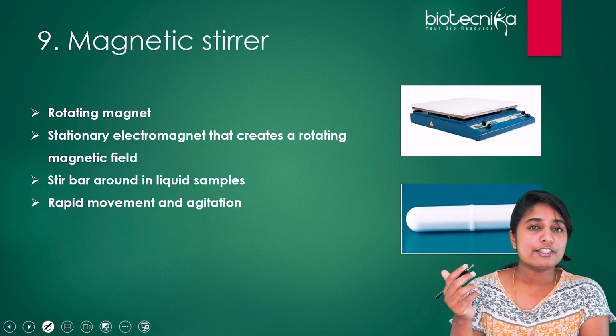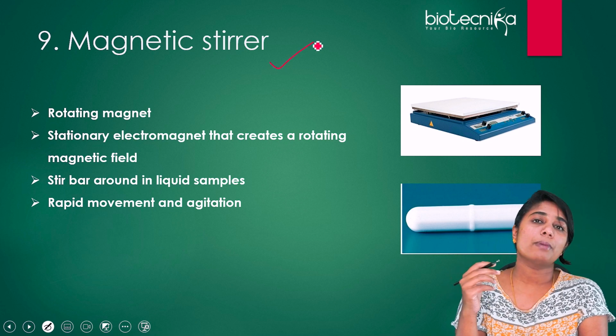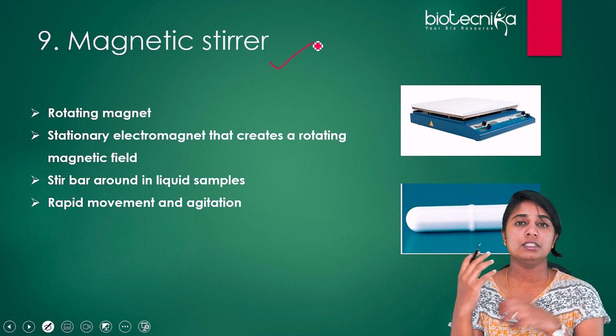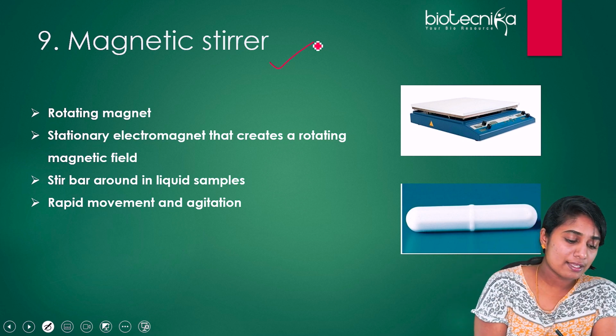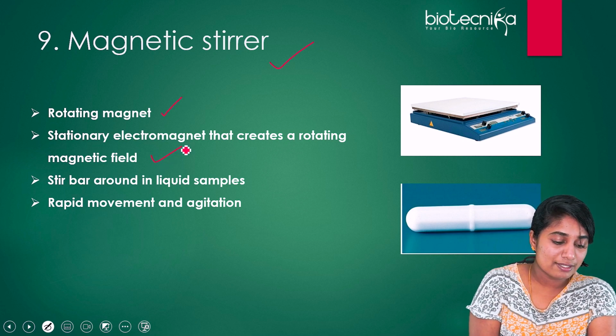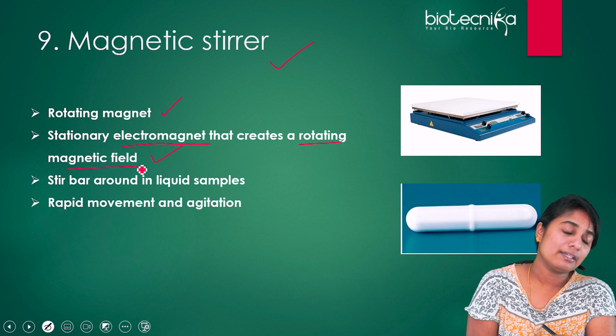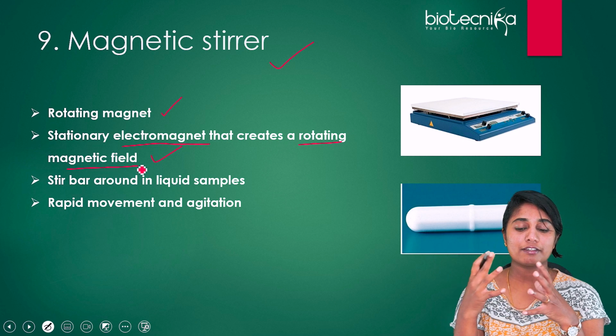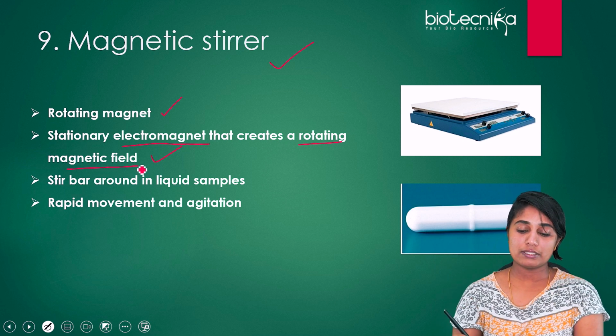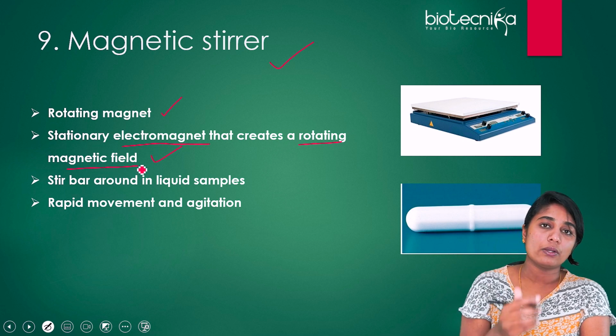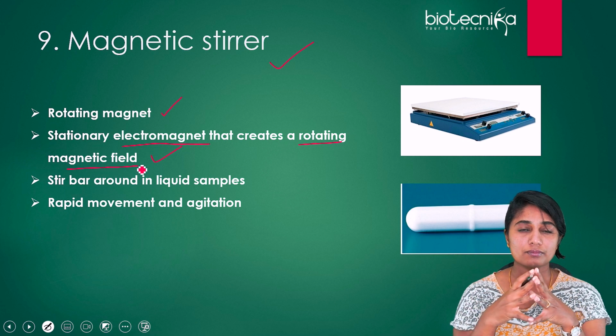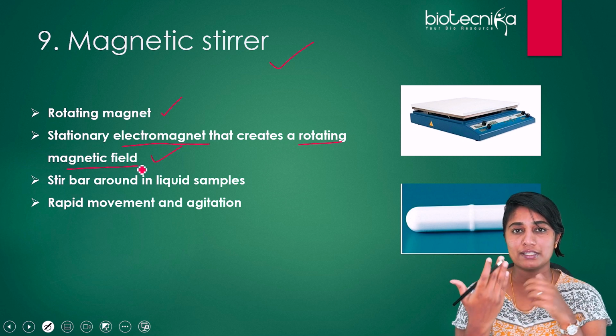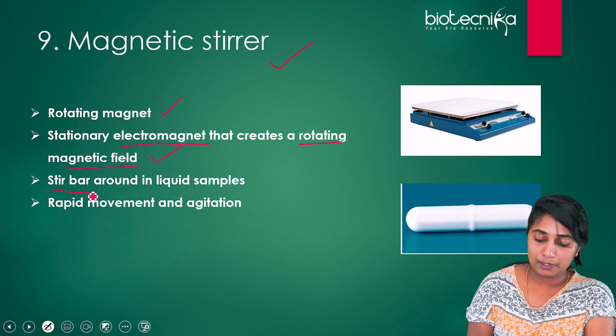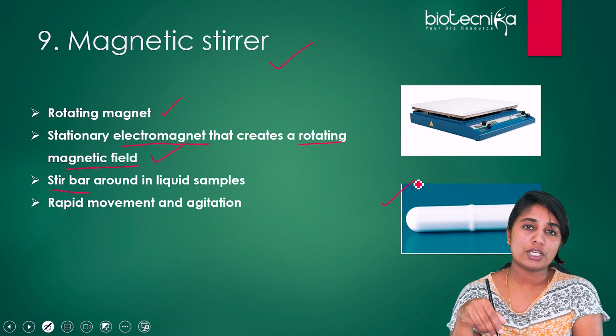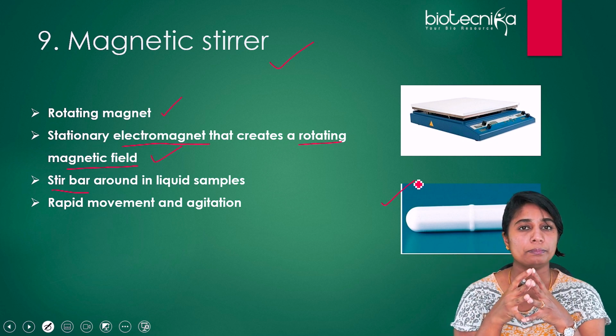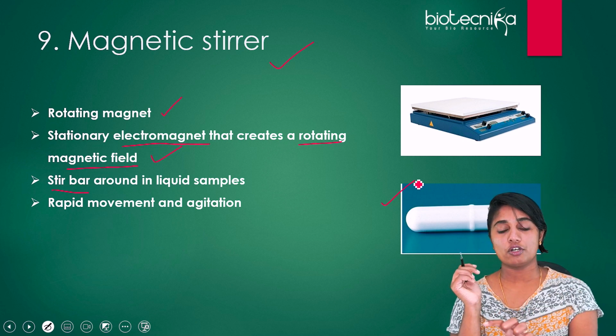Now, after the centrifuge, the next instrument we are going to talk about is the magnetic stirrer. A magnetic stirrer is used for stirring molecules, basically for agitation as well. It has a rotating magnet, or it can also have a stationary electromagnet that creates a rotating magnetic field. So basically we need a variable magnetic field in this particular instrument. Once we get a variable magnetic field inside the liquid sample where we want to mix the molecules by stirring, you place something called a stir bar, which is seen in this image as well. You place this stir bar inside your fluid medium, and then you place the whole beaker on top of this stand.